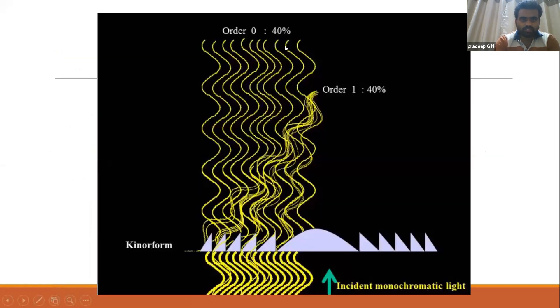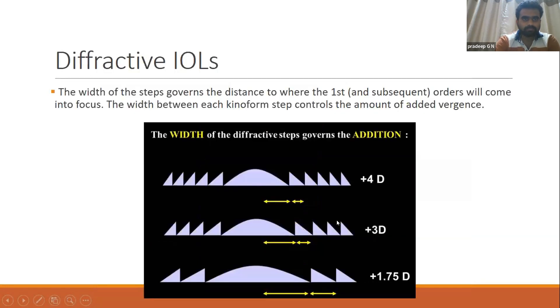Undeviated light constitutes zero-order diffraction, comprising 40% of incident light. Another 40% is deviated light used for the alternate focal point, and the remaining 20% of incident light is lost. The width of the steps determines the distance at which first-order diffraction comes into focus, while the width between each kinoform step controls the amount of added power.